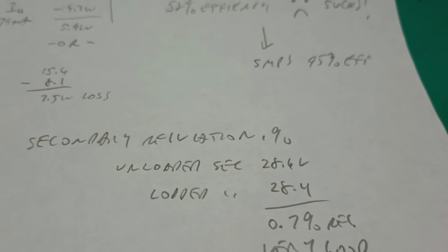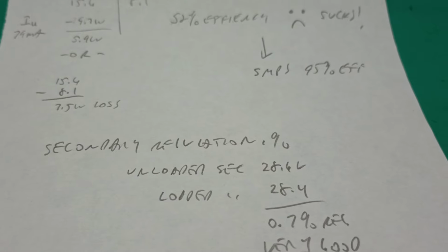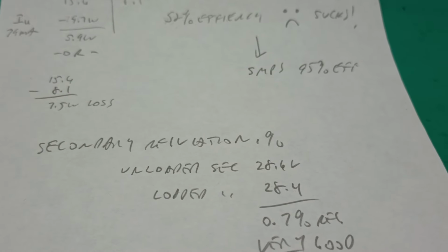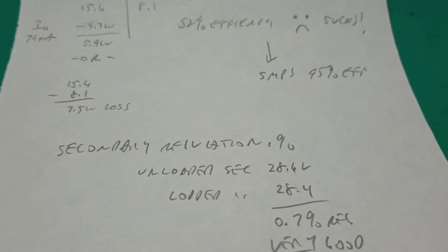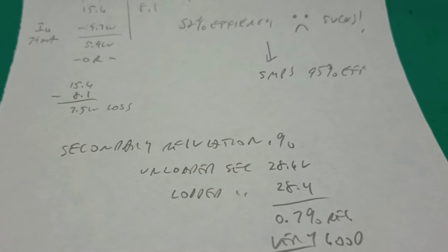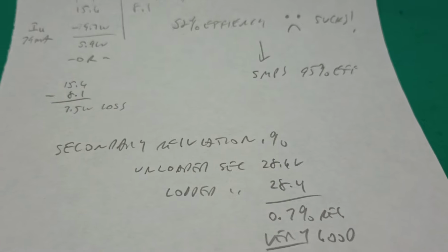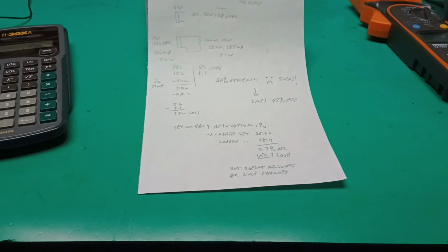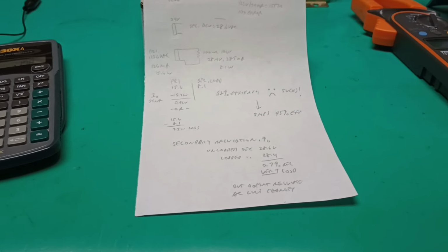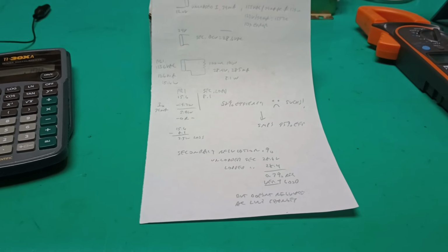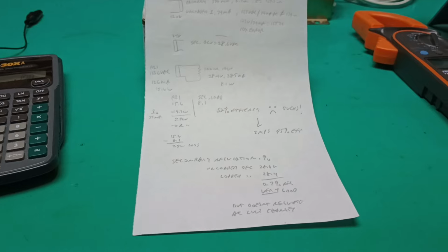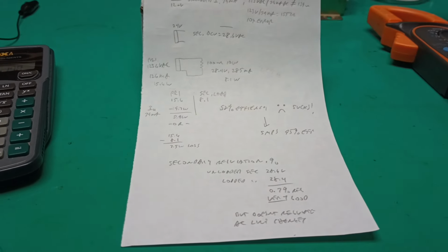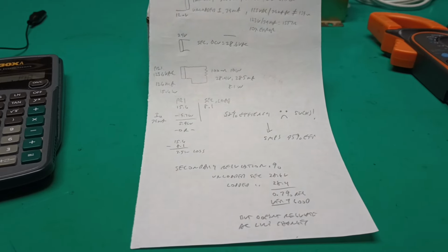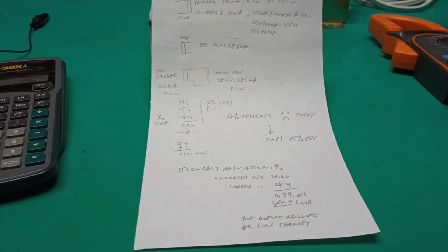Now this is still going to be subject to changes in the AC line voltage, which are give or take 10%. But that changes either relatively slowly or at times of the day, like evening when people come home and start turning loads on. The line voltage might drop sharply at 5 or 6 p.m. So do this testing midday, and the AC line is going to be pretty stable. It's been a couple hours. It's only varied about a volt, which is a little better than 1%. So overall, this will be a very well regulated system. But it won't have any solid state devices in it except high voltage diodes.